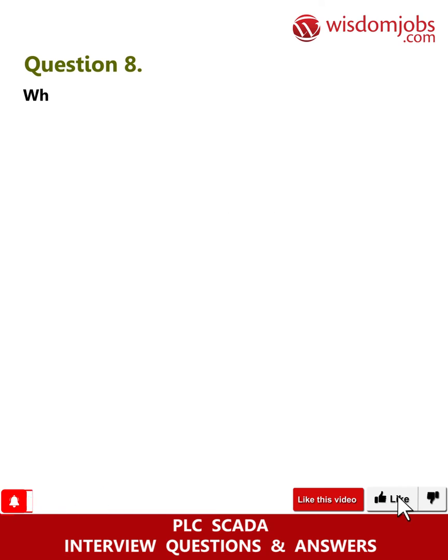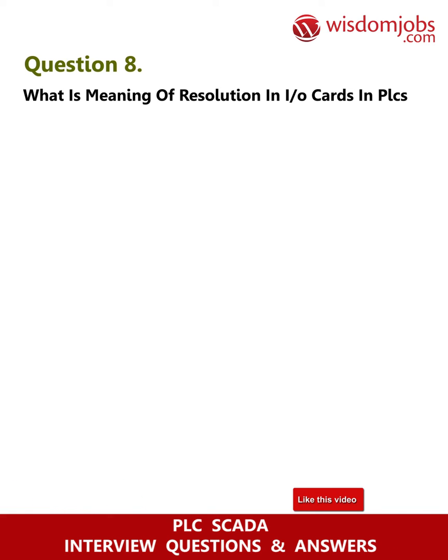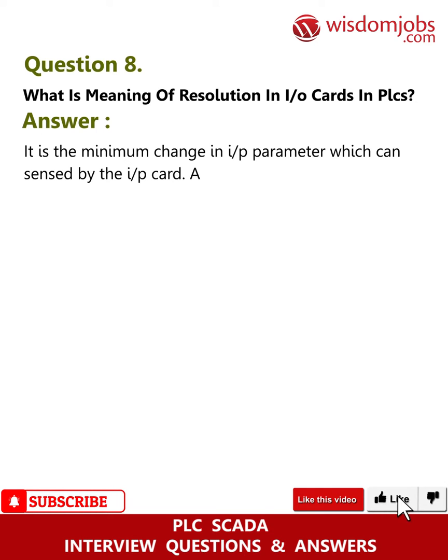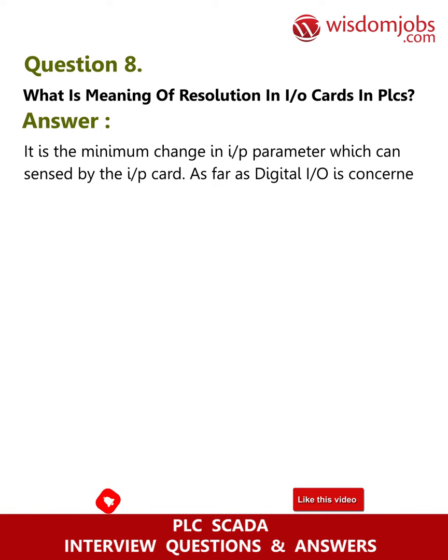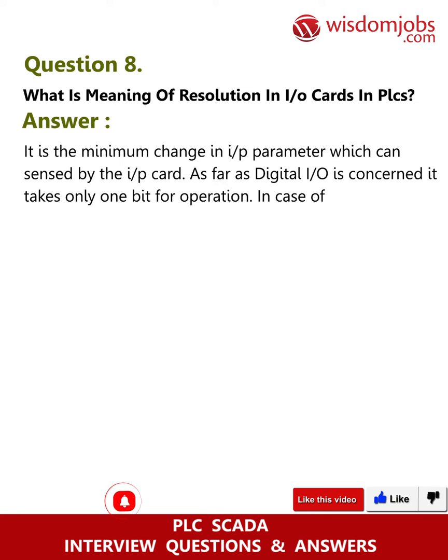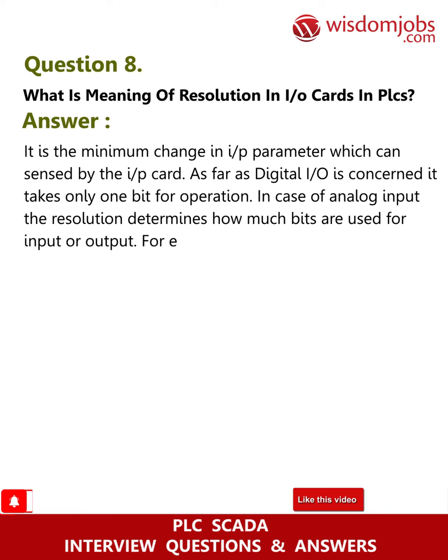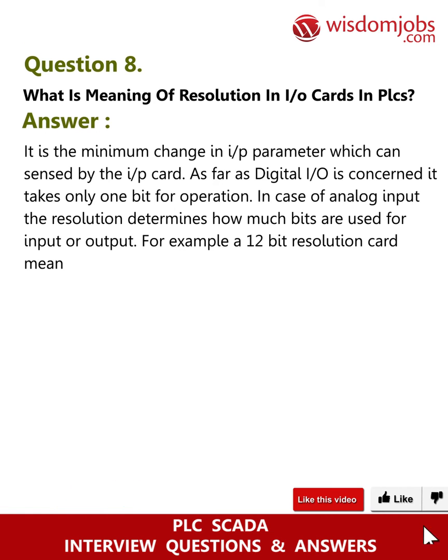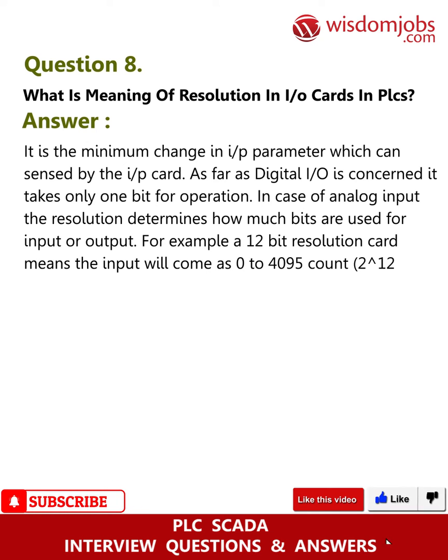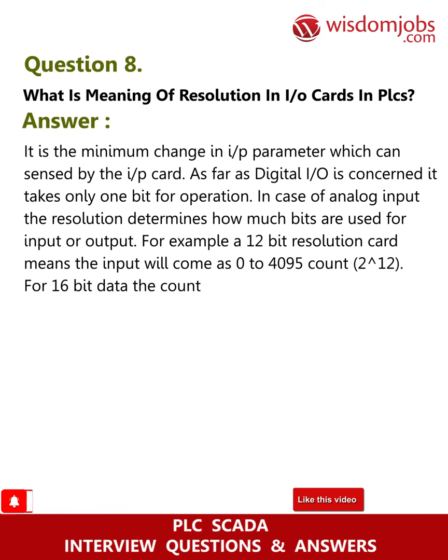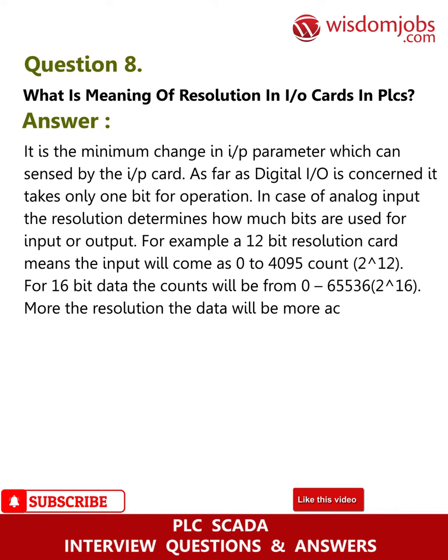Question 8: What is the meaning of resolution in IO cards in PLCs? Answer: It is the minimum change in an input parameter which can be sensed by the input card. For digital I/O, it takes only one bit for operation. For analog input, the resolution determines how many bits are used — for example, a 12-bit resolution card means the input will range from 0 to 4095 counts, while 16-bit data gives counts from 0 to 65536. More resolution means the data will be more accurate.